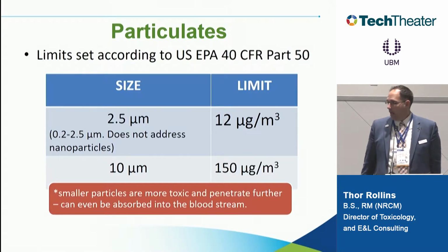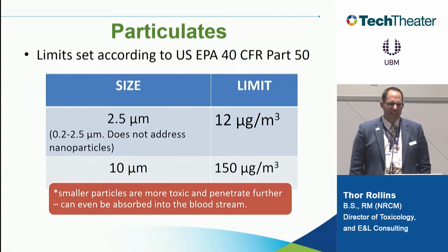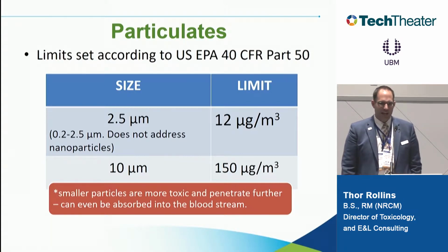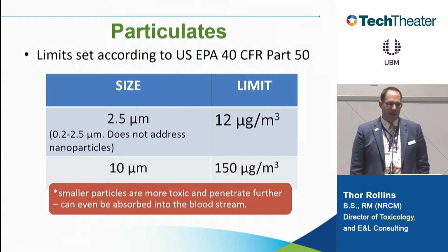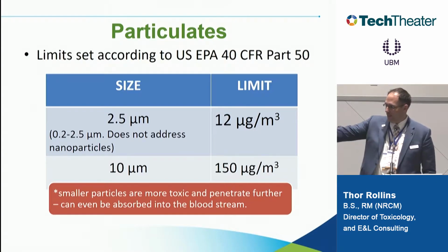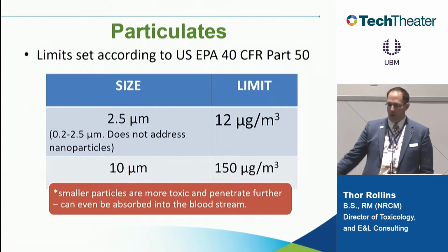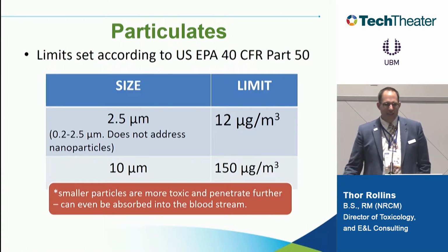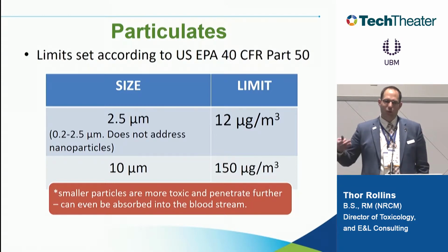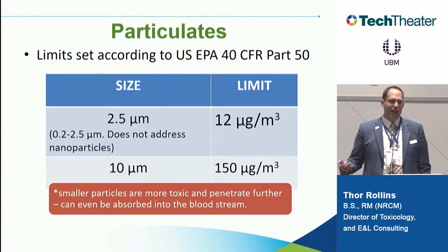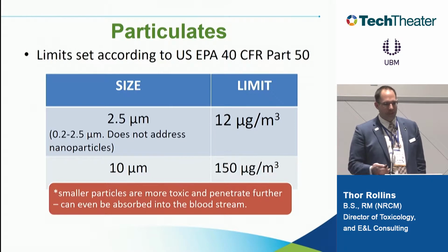But then there is no good acceptance criteria for particulates. If you're looking for one for a medical device, the best one we have is this USP acceptance criteria. We use this one, but this is for containers for injectables, and it's just not great. But the FDA has allowed us to use these limits to help to prove safety.